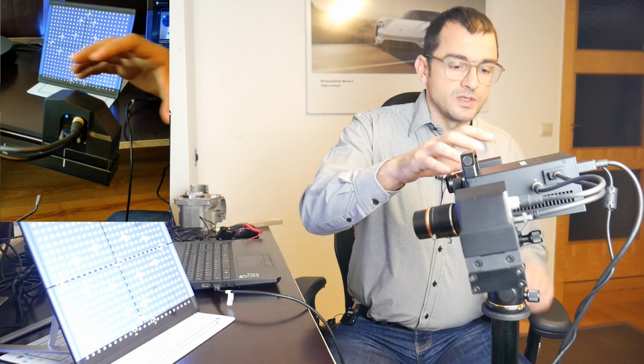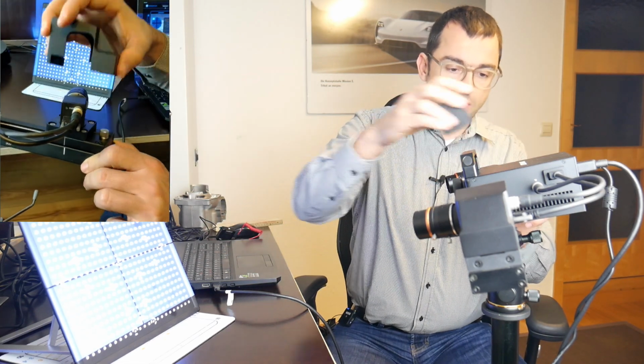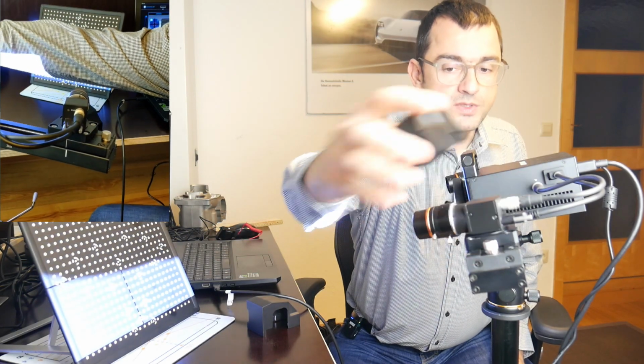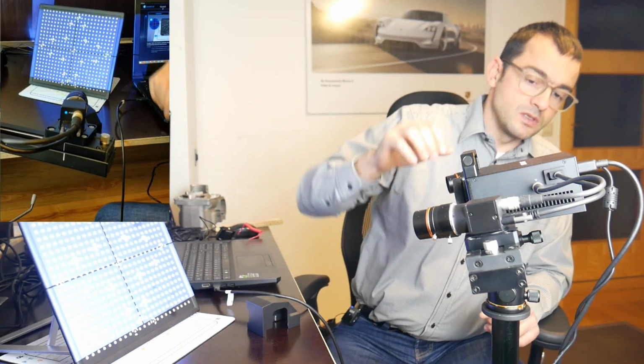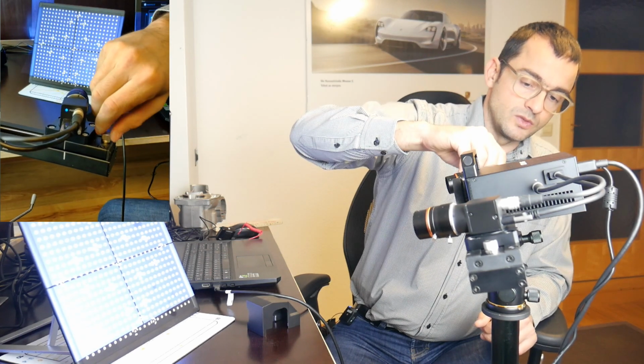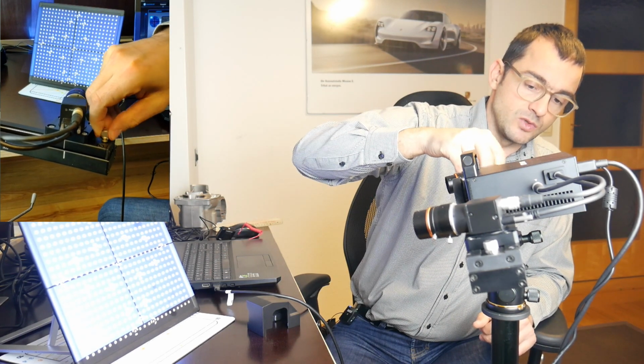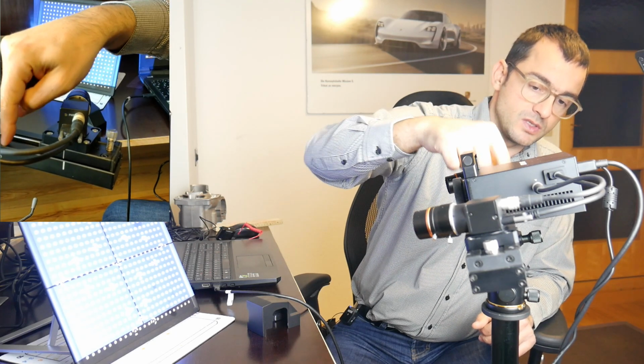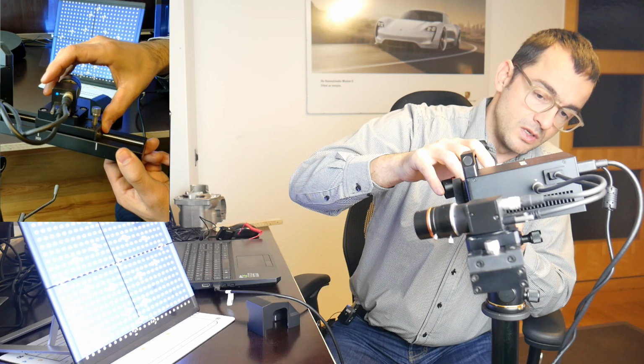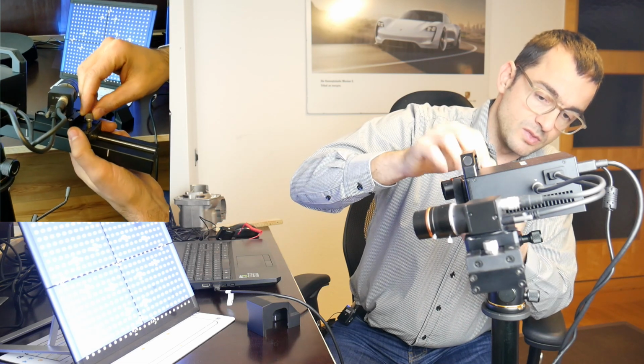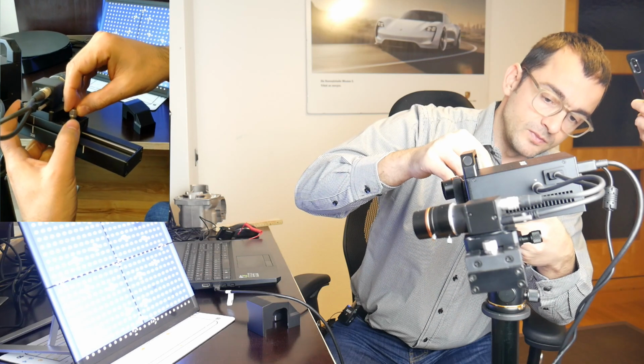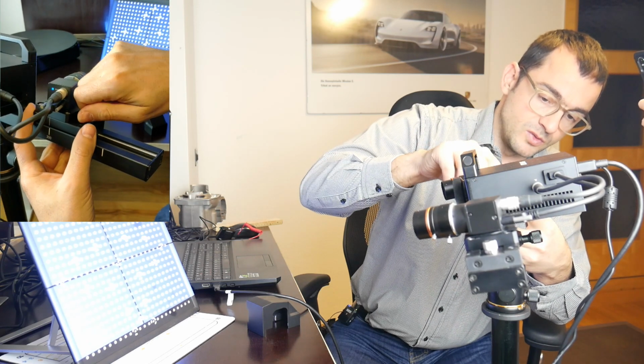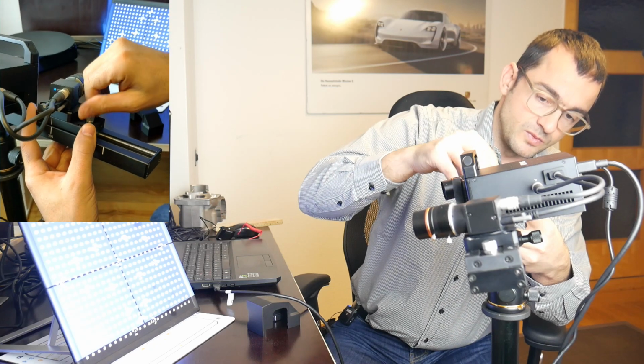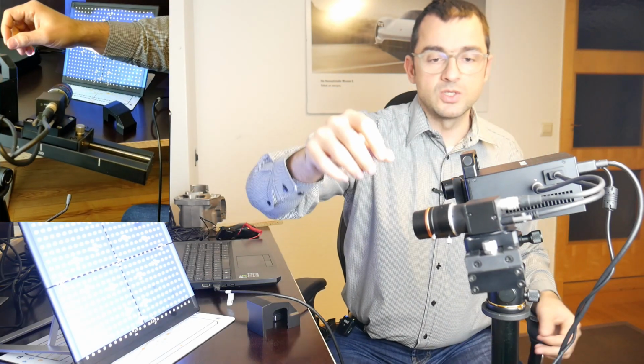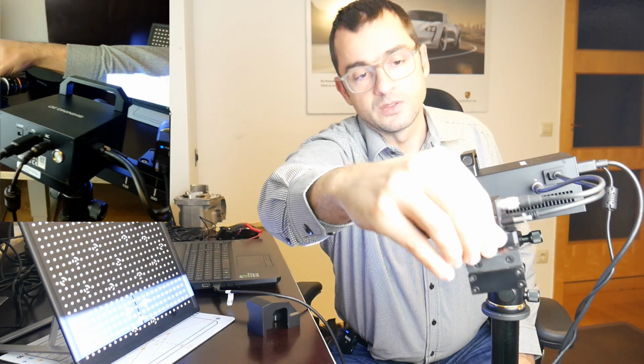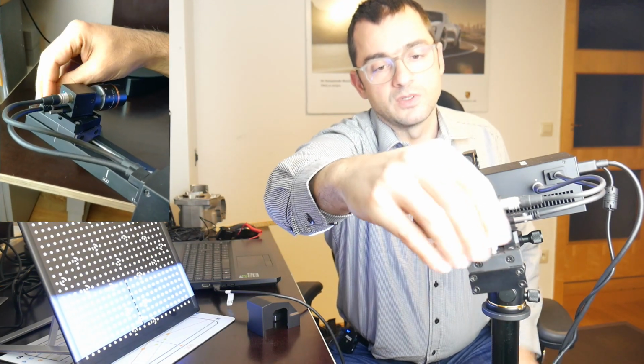So if you take the Transcan C out of its box, you first have to select the distance of the scanning field that you want to use. In this case, I'm using the most common one, that's 300 millimeters. That's the width of the scanning field more or less that you will achieve, and I'm going from the transport distance or the initial distance, which hopefully will be another scanning field soon, to my destination. That would be 300, and I do the same on the other side.